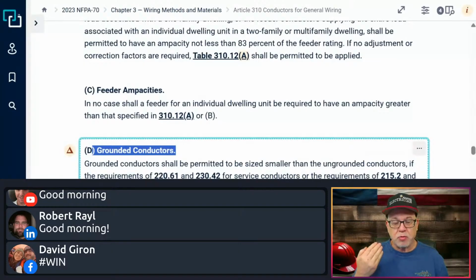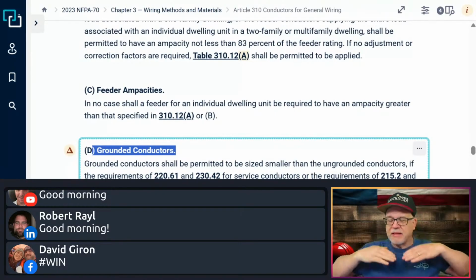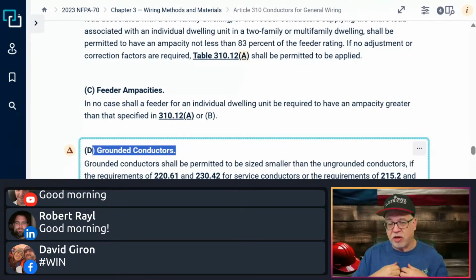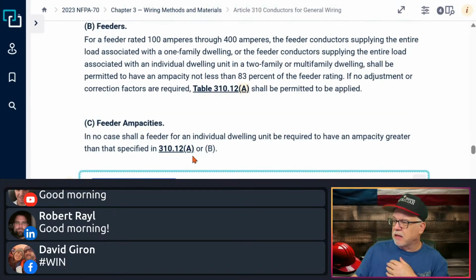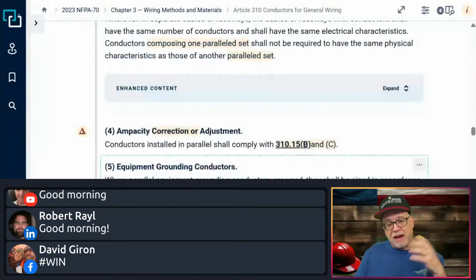And since we're only pulling partial conductors from a three-phase system, the two hots and a neutral derived from it, you will have a situation where the neutral can carry equal to or greater than any current that the phase conductors could carry. So we don't get to meet the allowances of D. So typically an engineer will just full-size the grounded conductor in that scenario, if you happen to be dealing with a single-phase 208/120 that's being derived from a three-phase system.